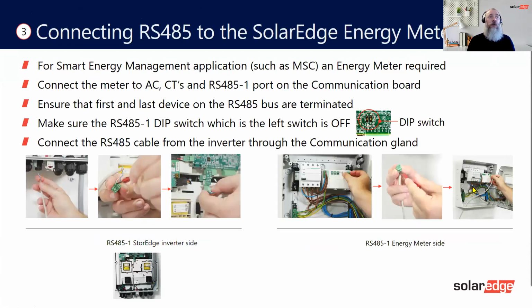So once you've done all of that, you've then got the RS485. I've showed you where the dip switches are on the communication board to start with. This is the meter, which you're familiar with. If you're not familiar with it, we do cover this later on. You simply wire a BAG connection. So you can see on here, B, A, G is ground. I think the B is minus and the A is positive, and that's ground.